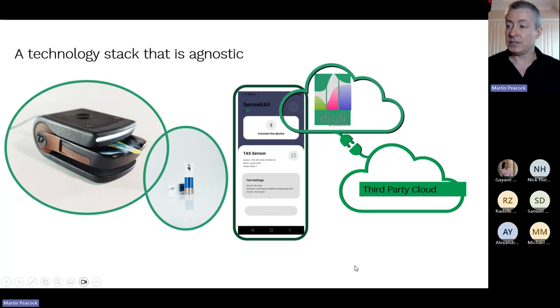The technology stack is agnostic — we don't really mind what assay or analyte you want. Electrochemistry is broadly applicable from small molecules to proteins to ions. People also need to develop the assay itself — will it be voltammetry, square wave voltammetry, or differential pulse voltammetry? There's also the calibration routine: how to turn raw signal into meaningful units like mg/dL, millimoles, or parts per million.